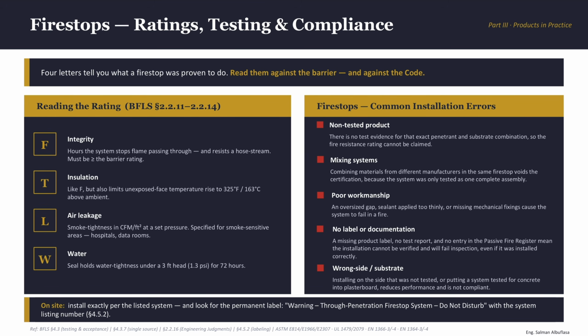And additionally, we have optional but critical performance tests, just like the water, W, and the air leakage, L. And the L rating is obviously the smoke tightness, smoke leakage performance. That means that I don't want smoke passing from one compartment to the other. And W rating means water resistance.